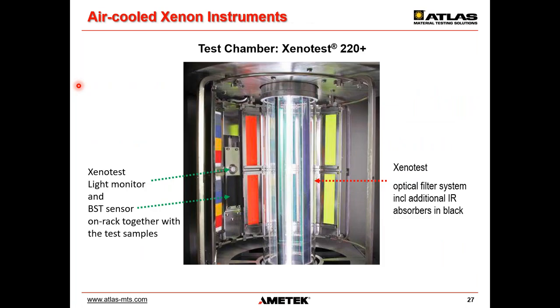The difference between air-cooled and water-cooled instruments, I said, is the lamp type, but it's also the way we measure the irradiance. Irradiance is measured in air-cooled instruments really on the sample rack, which is quite useful, we think, to measure exactly the irradiance where your samples are positioned.